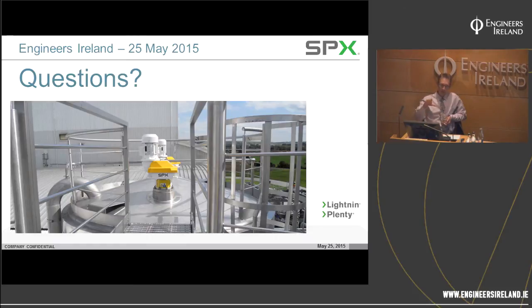So with a single down pumping impeller in the middle of the tank, assuming it's a baffled tank, what you're trying to do is achieve a top to bottom single loop flow pattern. So I would say best practice in terms of additives is at the top, into the suction side of the impeller. If that's not an option, then maybe somewhere in the strong upflow section would give you the same thing, because it would be rapidly incorporated into that loop.